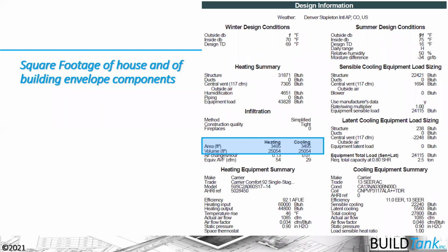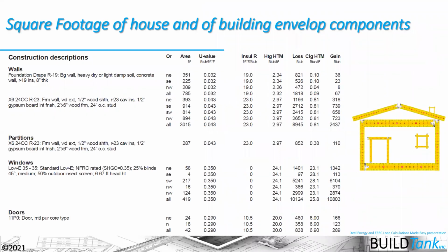If I have a 1,000 square foot house, obviously an area of 3,495 doesn't make sense, and the volume doesn't correlate to that size house. And similar if I have a really large house. We can also look at the actual components. There are these worksheets that come out of Manual J calculations through the software. And if I look at the area of this wall system and the windows that have been added, do they make sense for the house that this design is working for? Or are they over calculating the wall area or under calculating the wall area? We want to look at both of those things here.